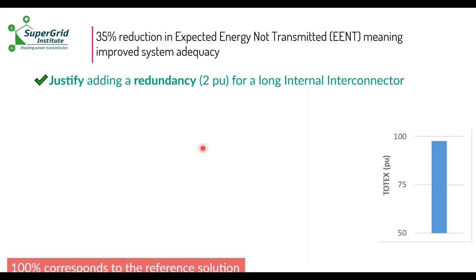So when comparing this kind of architectures, at the end we compute the total expenditure, what you were saying, the total life cycle cost of the system. You can see that in an example where you need to put a redundancy on an internal interconnector, so when you put two DC lines, for example, with respect to the original case scenario, which is 100%, you need to spend a little bit more. First, you have a little bit more losses here, 1% more, and you need to spend 4.5% more. So you have a capex increase as well.